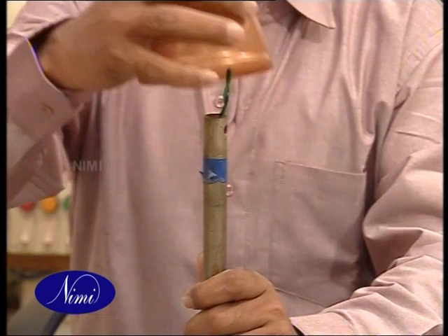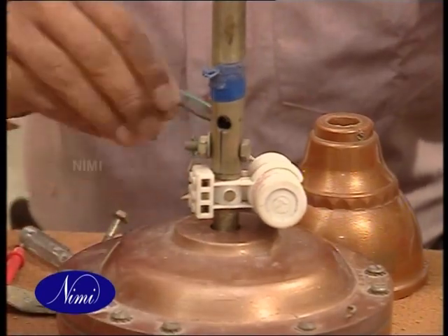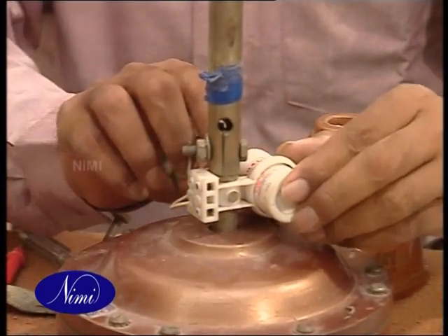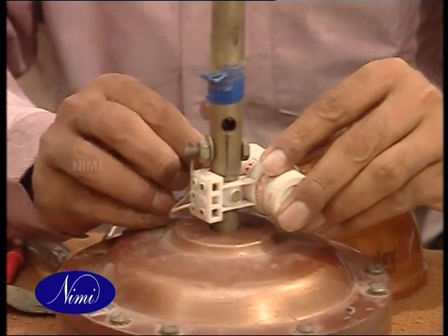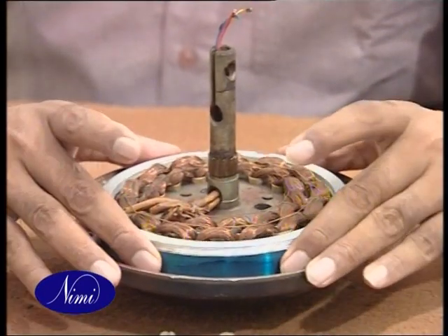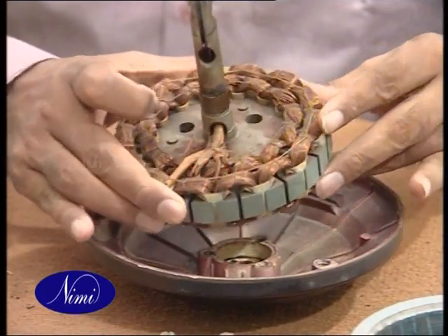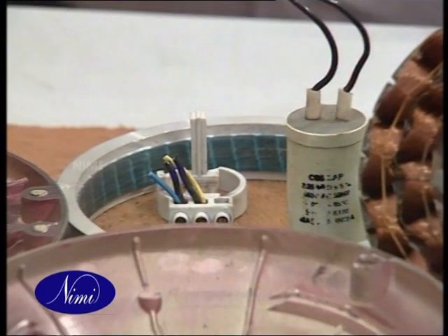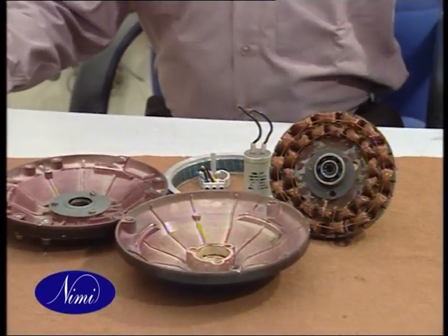Separate the down rod along with the canopies from the capacitor housing. Remove the split pin and set screw. Next, remove the capacitor from the housing. Mark and unscrew the cover fixing screws and separate the bottom cover and the rotor. Pull out the rotor and the stator from the top cover. Inspect all the removed parts. Replace the defective parts and reassemble the dismantled parts in the reverse order.